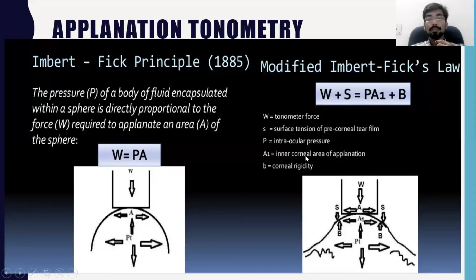Modified Imbert-Fick law is W plus S is equal to PA1 plus B, where W is tonometer force, S is surface tension of precorneal tear film, P is intraocular pressure, A1 is inner corneal area of applanation, B is corneal rigidity. So when A1 is 7.35 millimeter square, S balances B and W is equal to P. This inner area of applanation is achieved when the diameter of the external area of corneal applanation is 3.06 mm. So grams of force applied to flatten 3.06 mm diameter of cornea, multiplied by 10, is directly converted to IOP in millimeter of Hg.